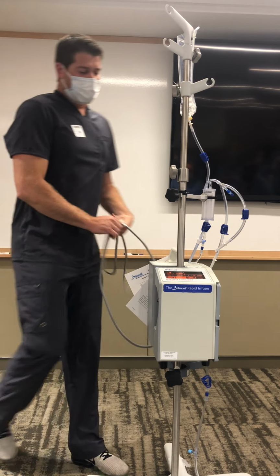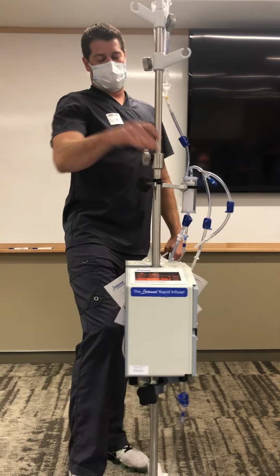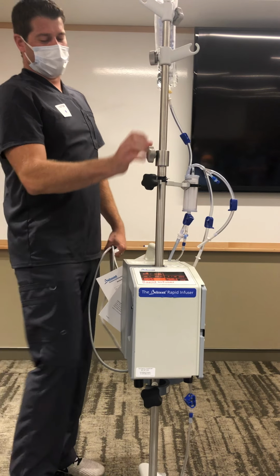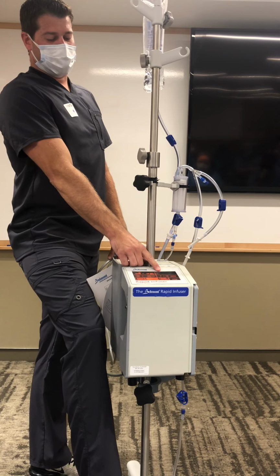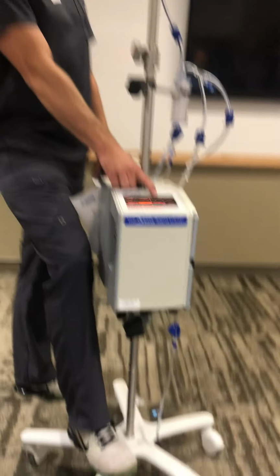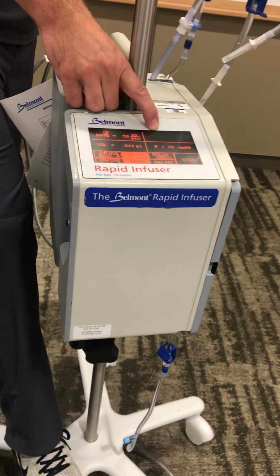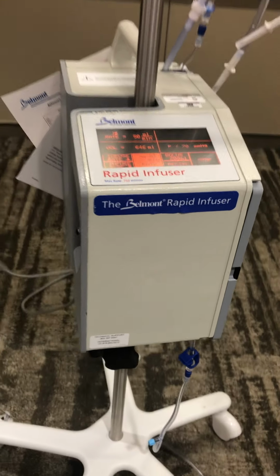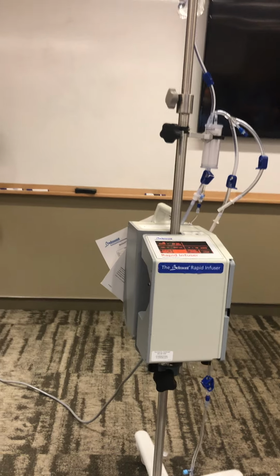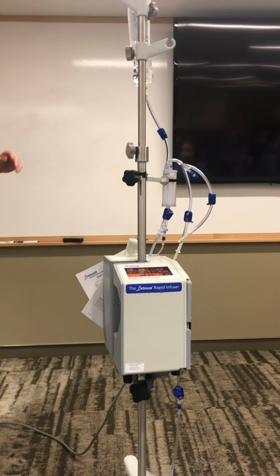So this machine has 30 minutes of backup battery power, of which you can infuse at a max rate of 50 mLs a minute. However, when it's on battery power, notice it's flashing no heating, so it does not actively warm on battery power. So the workaround for that is the recirculate button.